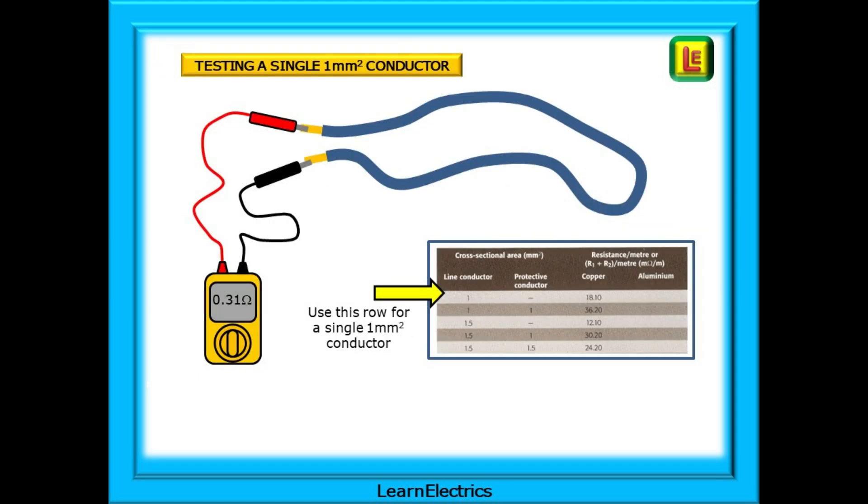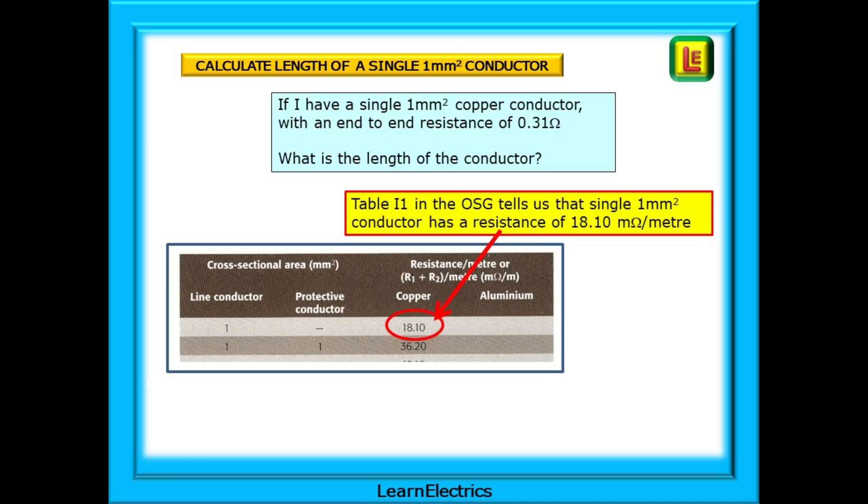Let's begin with testing a single one square millimeter conductor as an end-to-end test. There is only one cable and we should therefore select the correct row from the table. The row with one for the line and nothing else, just a dash for the protective conductor. A question then. If we have a single one square millimeter copper conductor with an end-to-end resistance of 0.31 ohms, what is the length of the conductor? Using table I1 in the on-site guide and selecting the correct row, we're told that a one square millimeter conductor has a resistance of 18.10 milli-ohms per meter length.